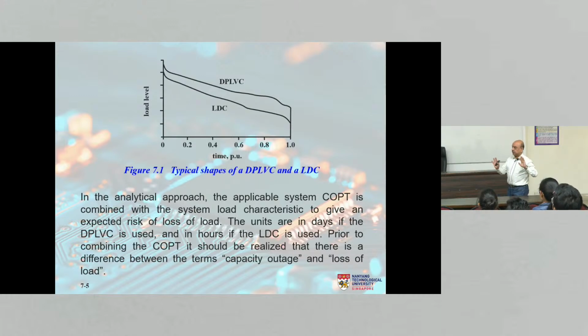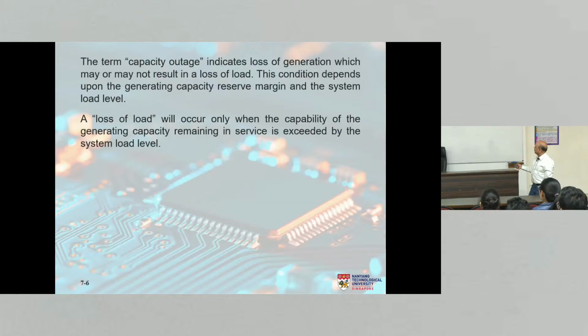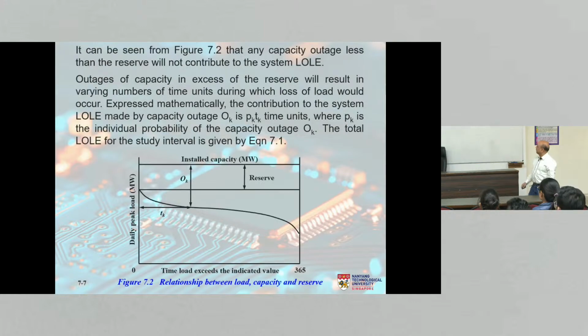So we must make sure that we understand these two terms correctly. The term capacity outage indicates loss of generation which may or may not result in a loss of load. Yeah, it could, it may not, okay? So loss of load only occurs when the generating capacity is less than the load. So now let's try and understand this from this particular figure.